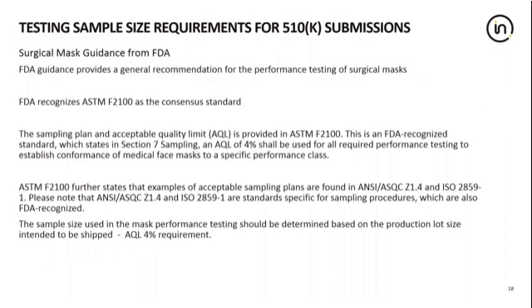The FDA provides a general recommendation for performance testing needed to support surgical masks, but it does not specifically discuss the sampling plan which should be used. However, the FDA does recognise the sampling plan which is included in ASTM F2100, which recommends a 4% AQL. And this is recommended to establish performance requirements for medical masks.